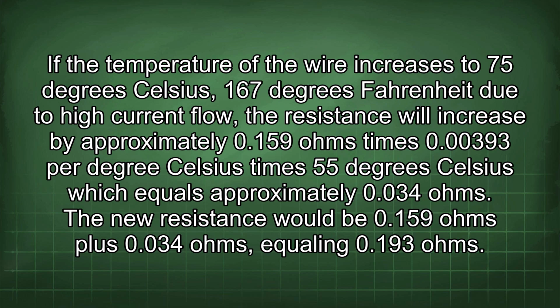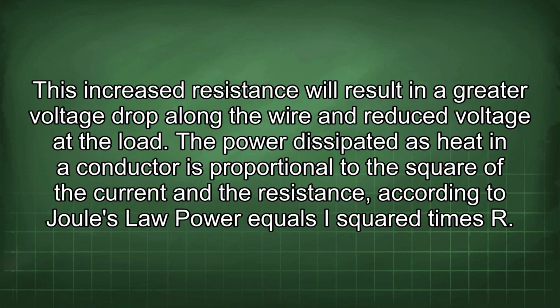0.159 ohms times 0.00393 per degree Celsius times 55 degrees Celsius, which equals approximately 0.034 ohms. The new resistance would be 0.159 ohms plus 0.034 ohms, equaling 0.193 ohms. This increased resistance will result in a greater voltage drop along the wire and reduced voltage at the load.